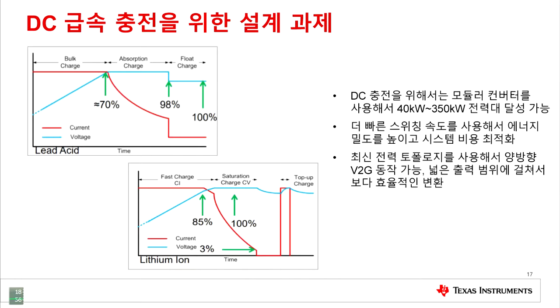Looking at the charging profile of a lithium-ion battery: to get up to around 85% charge, you run constant current mode, then you change over to get the rest of the charge in, or top-up charge, with constant voltage. That means you have to have very accurate control on both the current and voltage side, with the high power in place, with monitoring, to achieve an accurate charging curve.